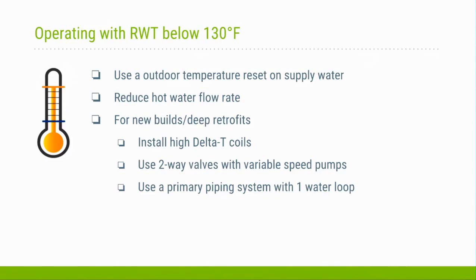Okay, so to continue on that note, because it's an important one, here are a couple of recommended practices to ensure that. One easy one, which really is a controls implementation, is to use a reset on supply water temperature based on outdoor air temperature. For the coldest day of the year, your design day, you need to be supplying your water temperature maybe at 180 degrees F. But as it gets warmer outside, you don't need that really hot water. And so you can do a controls programming intervention, almost no cost, that will reset your supply water temperature set point to lower values as the outdoor air temperature goes up. So maybe when it's 50 out, you only need to supply 150 degree water. What that does is ensure that you're getting cooler temps back and increasing your efficiency.